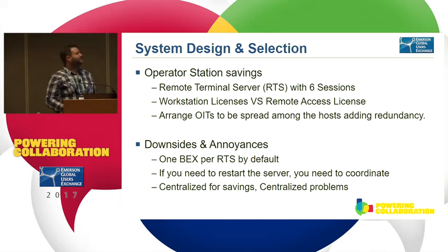All right. So we did also consider, hey, it's virtual. Why can't we run 128 virtual machines? Well, we'd have to add about 6 hosts. So we decided we have a lot of operator stations. They're going to be lightly used, probably just 1 session out of every 6. We went with the terminal server, so if it gets bad, we can utilize all of them. But in general, it's a light loading. We can get away with spreading it thin.